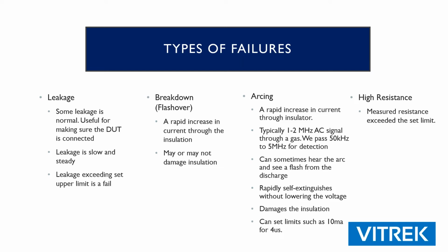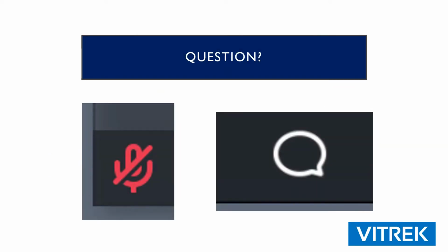We can set limits around the amplitude and the duration of those arcs, and as of last month, we can actually count them. We released a new firmware tweak for one of our customers that allows us to count the number of arcs that occur during a test. And then obviously high resistance: if you're doing any of those continuity or ground bond tests, you can just fail because the resistance simply exceeds your limits.